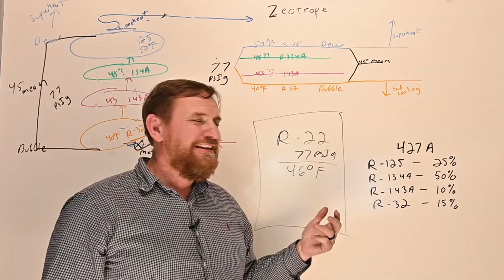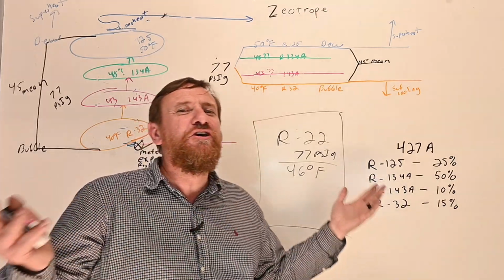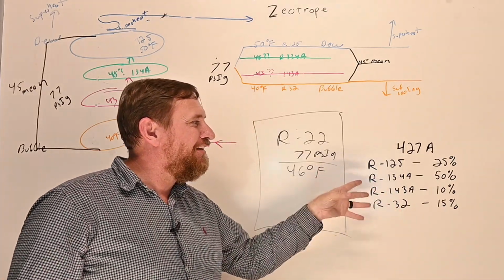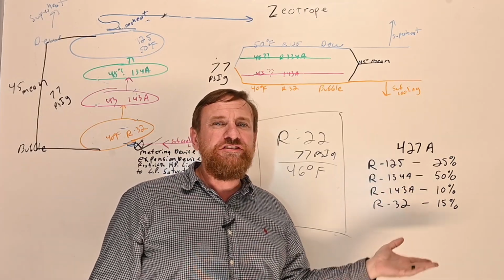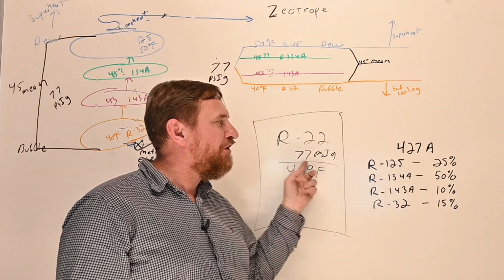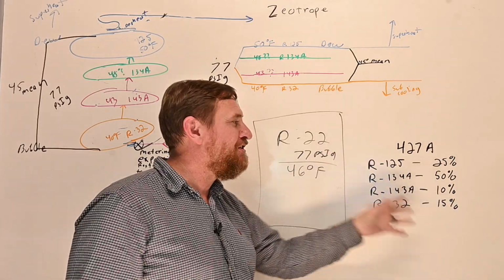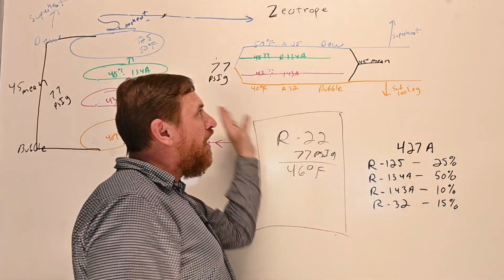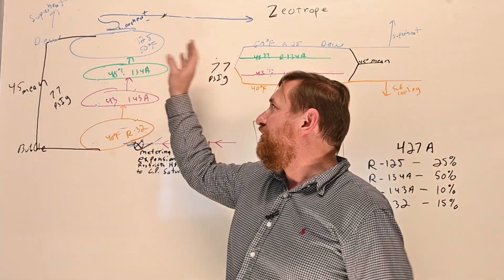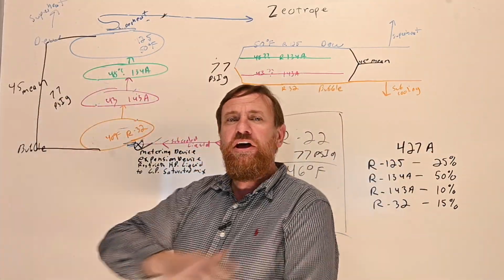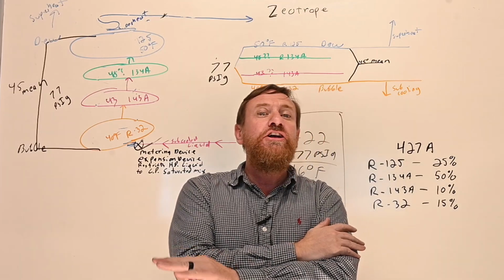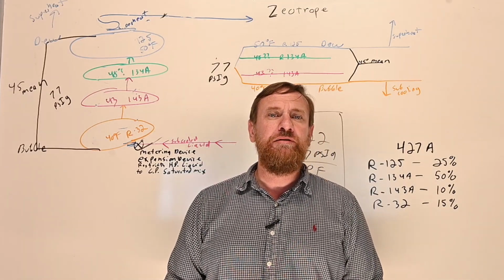That'd be what, a Cinco blend? I don't even know how that works. At that point, I'm lost and nobody knows what's going on. We don't even know the percentage of R22 in the system already that's going to be changing all of these percentages. So all of this is out the window. Our dew point, our mean, our bubble point, all that is completely gone. We have no clue where saturation is taking place.